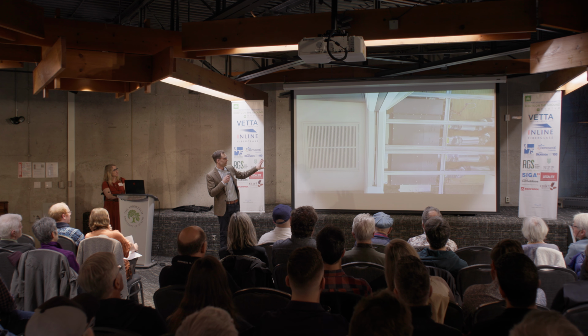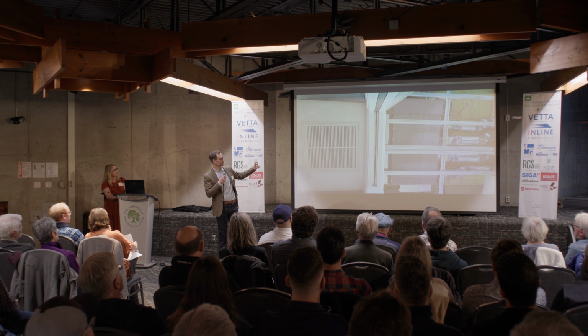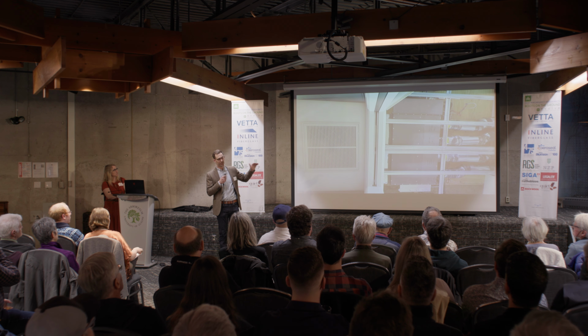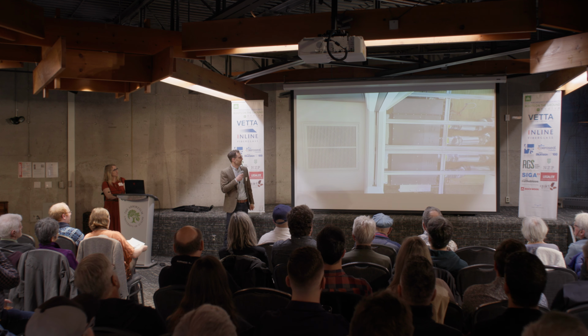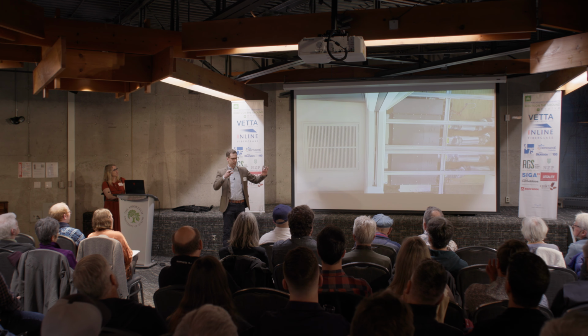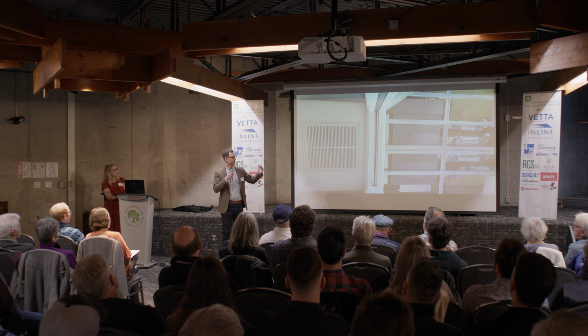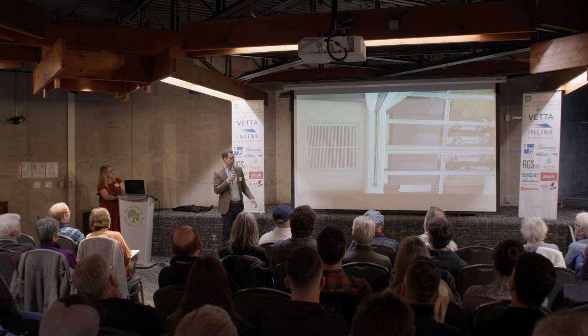So there's a pocket door in between that's louvered to provide an airflow pathway back to the return grill so we don't choke it. That is a standard 24 by 24 inch by 2 inch filter frame return, which is my favorite detail for return grills, because now rather than the long, skinny, weird filters that come with these units and all kinds of fan coils, we just threw those in the garbage.